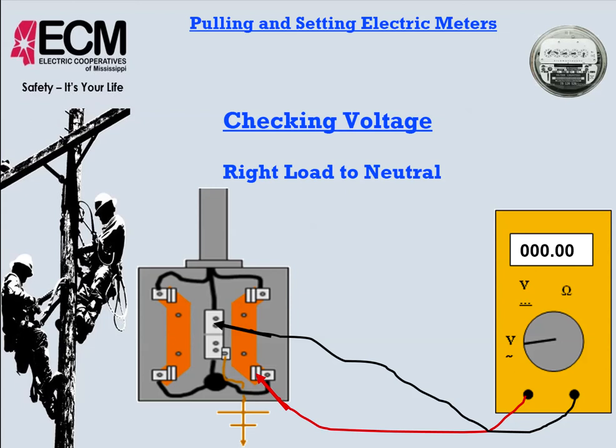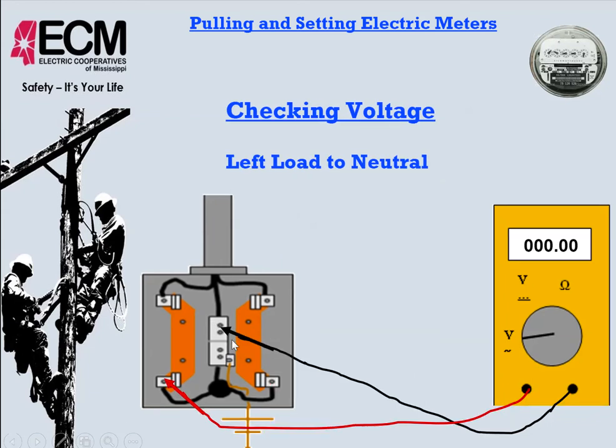I still say that we should not set the meter, but definitely should not set it energized if we cannot complete our checks. Okay, so the first thing that we want to do is check from, we've already established that this is the neutral, to the bottom side and make sure that it is not hot. Okay, it should read 0 volts. We have it set on volts. We're checking for voltage. There should not be any voltage on the bottom side of the meter base, and then we should check that on the other side as well, making sure that there are 0 volts here, and that the load side, left side, is not energized.